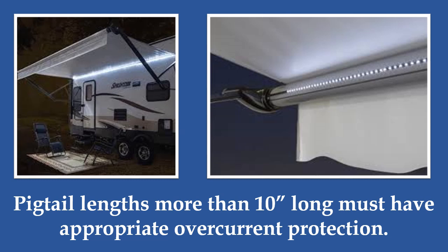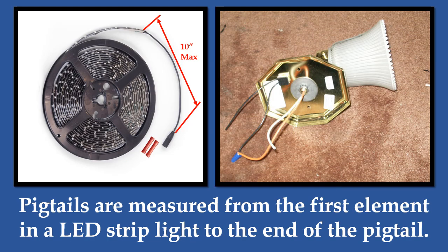This is the other exception. If the pigtail is less than 10 inches in length, no additional overcurrent protection is required for the pigtail that is less than 10 inches. So, how do you determine the length of a pigtail supplied with the lighting? Standard incandescents, fluorescents, and other lights are all measured from the bulb's receptacle connection to the end of the pigtail. With LED lights, the measurement starts at the first light element, as seen here in the photo on the left.